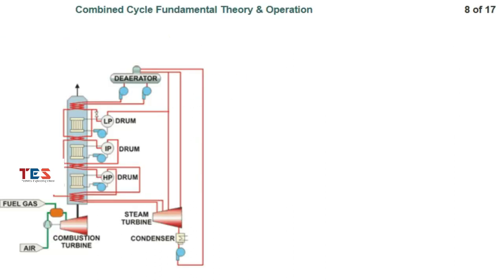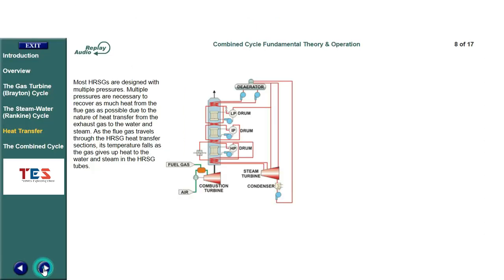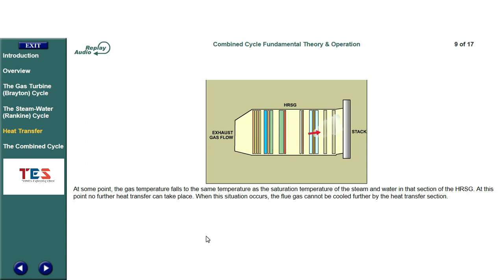Most HRSGs are designed with multiple pressures. Multiple pressures are necessary to recover as much heat from the flue gas as possible. As the flue gas travels through the HRSG heat transfer sections, its temperature falls as the gas gives up heat to the water and steam in the HRSG tubes. At some point, the gas temperature falls to the same temperature as the saturation temperature of the steam and water in that section of the HRSG. At this point, no further heat transfer can take place, and the flue gas cannot be cooled further by that heat transfer section.